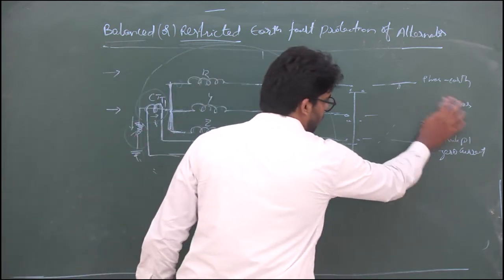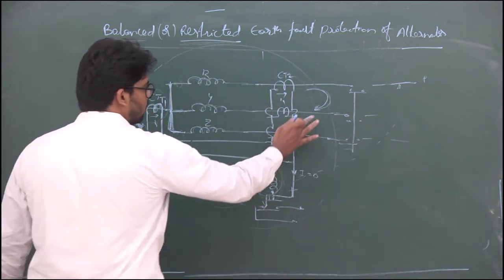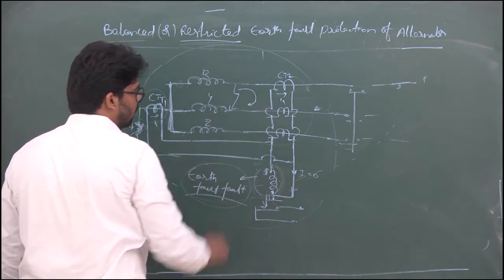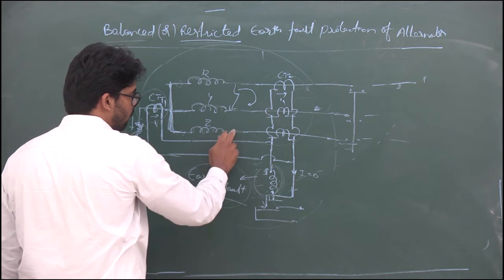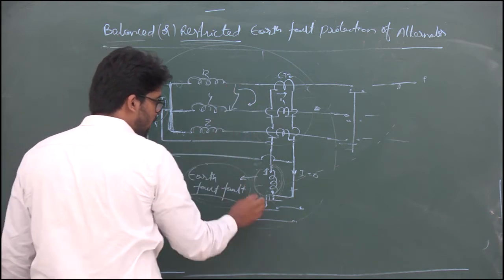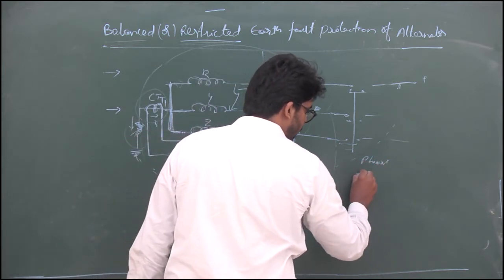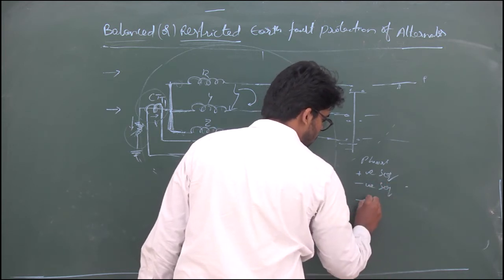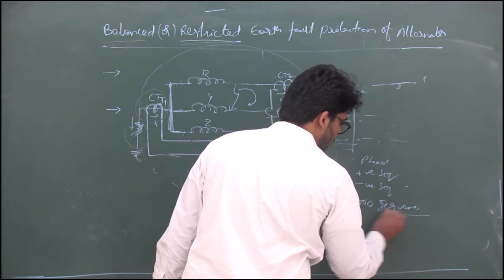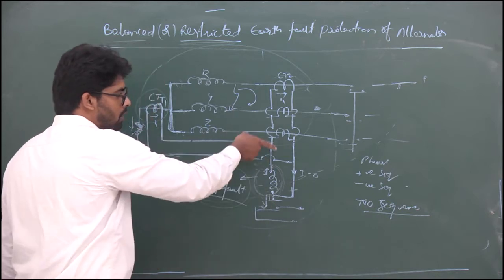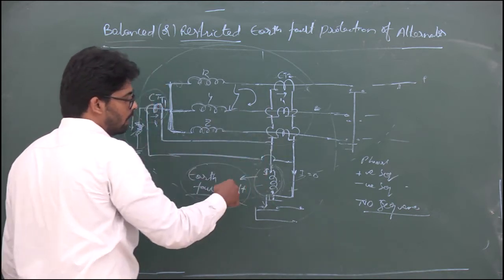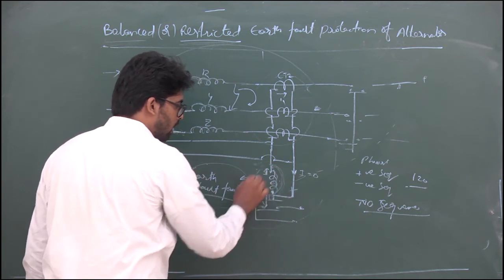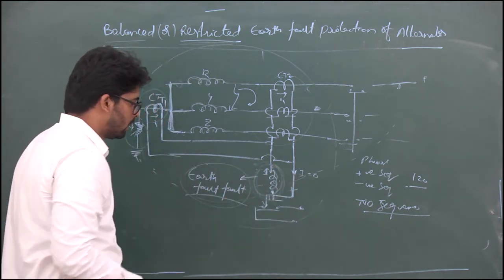For example, if a phase-to-phase fault occurs internally — so a phase-to-phase fault occurs here internally with a flow of current — when the phase-to-phase fault occurs we have a positive sequence and the negative sequence unbalanced component. There is no zero sequence component. This positive sequence and negative sequence unbalanced components will nullify each other with a phase differential of 120 degrees. Therefore there is no flow of zero sequence current to the relay coil, and the relay will not get operated.